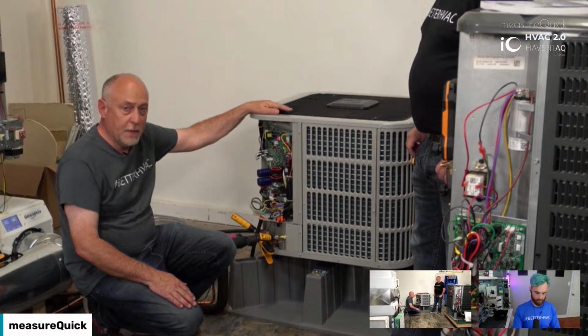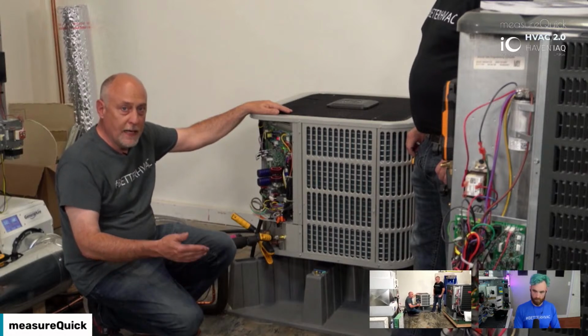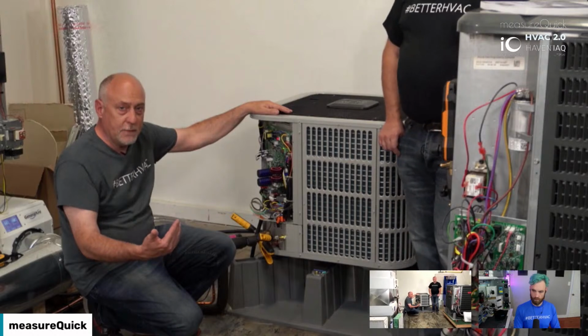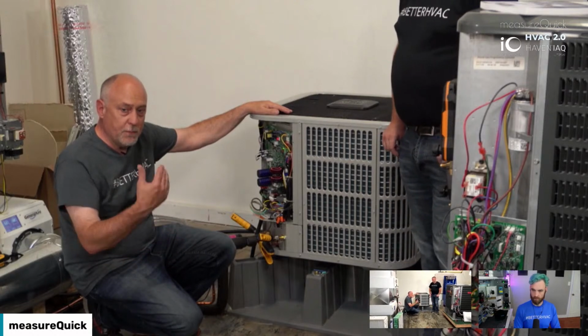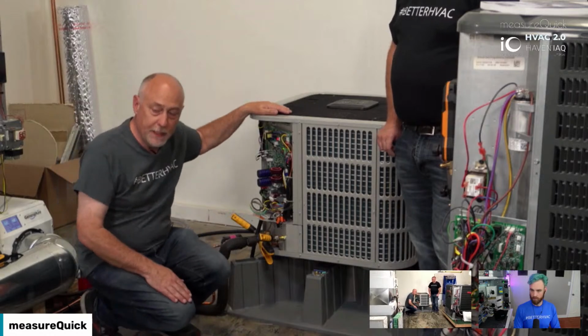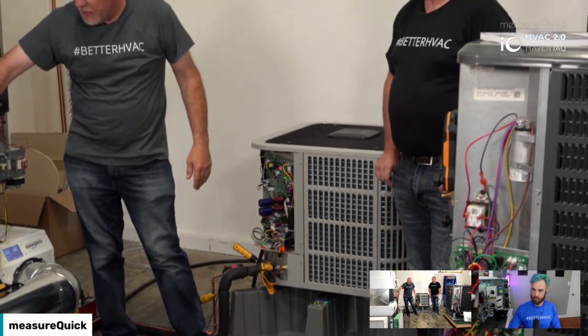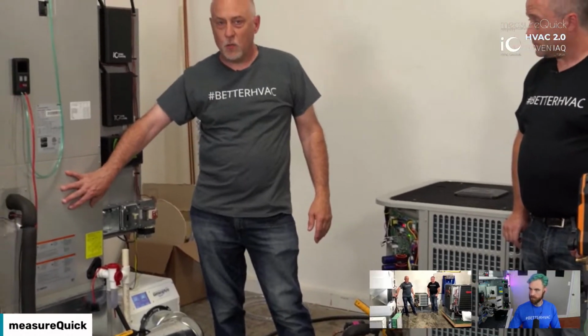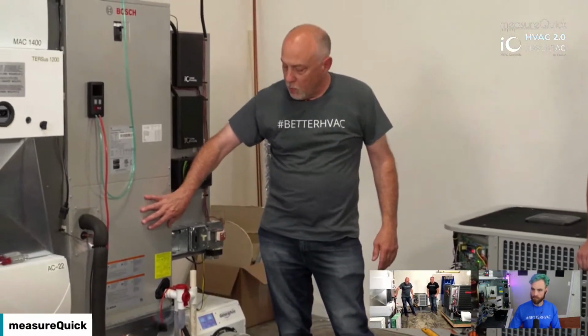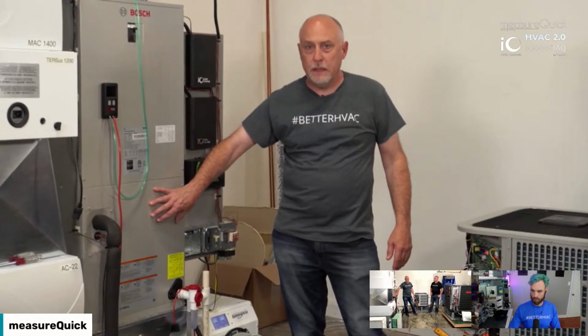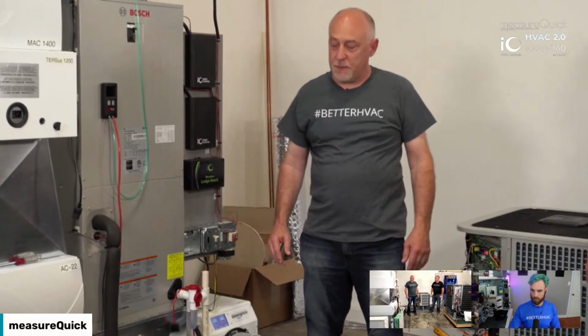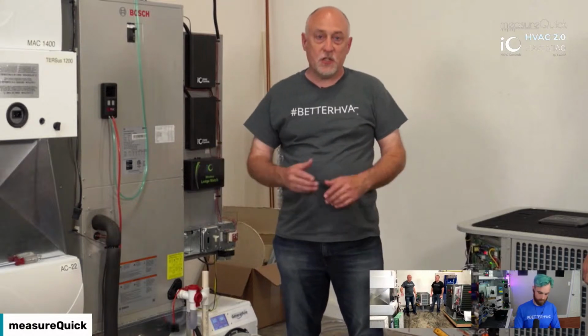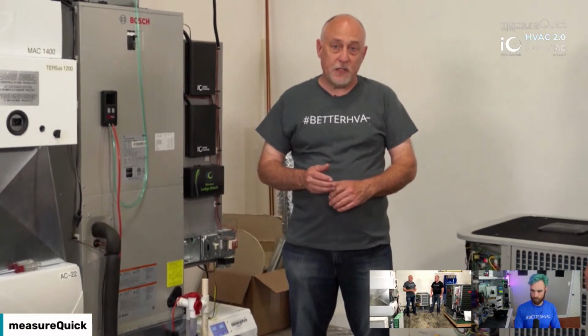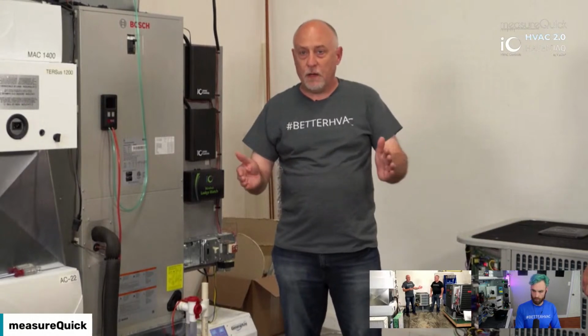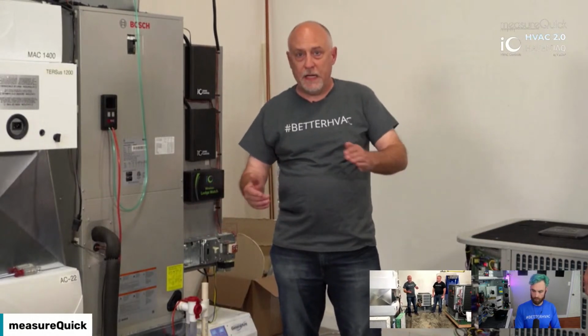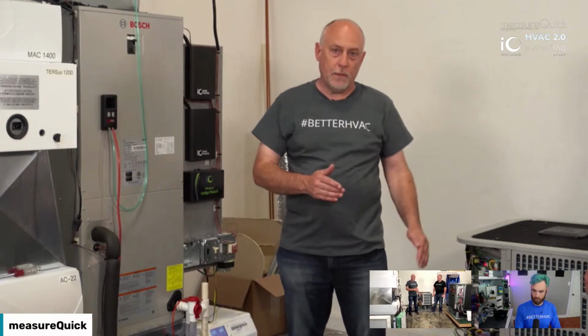And that's been a little bit of a problem, even in my own home, where we actually need the dehumidification once we're past midnight. Because what's happening is once the Bosch system shuts off, we're seeing two things happening. One of them is this entire evaporator coil is saturated, it's wet, and the moisture evaporates off this coil and basically reintroduces into the space. And then the second thing is there's just no sensible load for the system to start up again, so it'll be off for 5, 6, 7 hours, and we'll end up with high humidity, and then we have to take all day again to pull that moisture out.